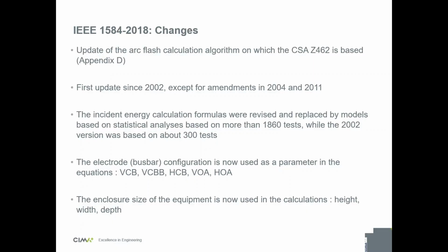A big change in the new standard is the new concept called electrode configuration. What is meant by electrode is the bus bars, the live conductors. This is now used as a parameter. It wasn't in the past. You have 5 configurations: VCB, VCBB, HCB, VOA, HOA. I will go through examples of each one and how to determine which ones apply to you.